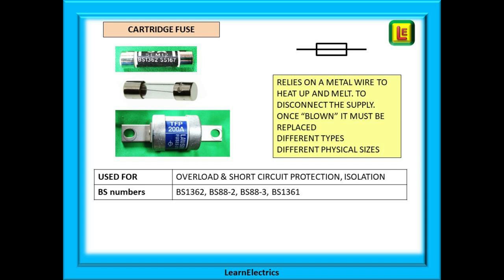Fuses come in different fusing types — some respond quickly to overcurrents, others respond a little slower, and this is achieved by mixing together different metals to make up the piece of fuse wire. There is a whole range of fusing sizes and many different physical sizes: push-in fuses, screw-in fuses, lugs with one hole, lugs with two holes, and even offset lugs. When buying fuses, take the old one with you to the wholesalers to make sure you buy the correct one.